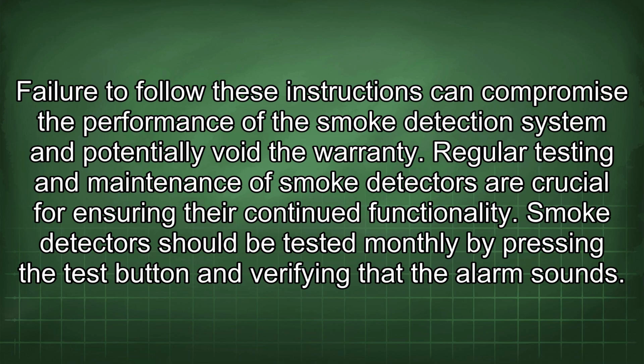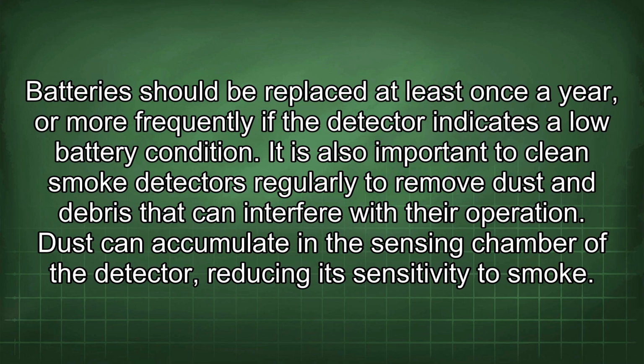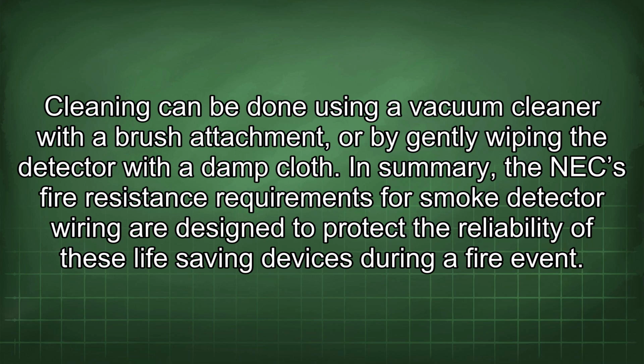Regular testing and maintenance of smoke detectors are crucial for ensuring their continued functionality. Smoke detectors should be tested monthly by pressing the test button and verifying that the alarm sounds. Batteries should be replaced at least once a year, or more frequently if the detector indicates a low battery condition. It is also important to clean smoke detectors regularly to remove dust and debris that can interfere with their operation. Dust can accumulate in the sensing chamber of the detector, reducing its sensitivity to smoke. Cleaning can be done using a vacuum cleaner with a brush attachment, or by gently wiping the detector with a damp cloth.